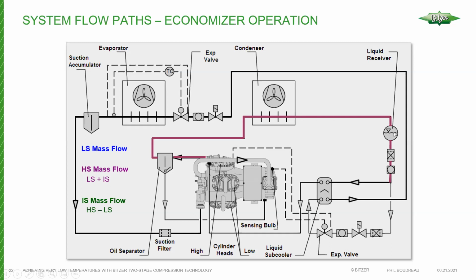And from this point, now we have subcooled refrigerant ends up in the receiver, just a buffer tank, if you will, storage, where that liquid level is going to float throughout the year, depending on load, depending on ambient temperature, depending on several things. And the idea is just to always have enough liquid in that receiver. But instead of just having that liquid travel to the evaporator now, in this case, we're going to split off our liquid line. So the blue line that comes off to the left, just after the sight glass, goes into the brazed plate heat exchanger, out of the heat exchanger, and towards the expansion valve.